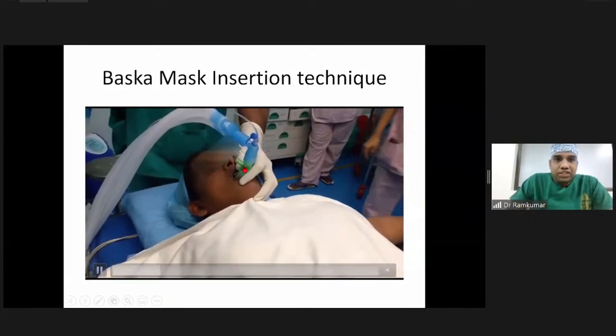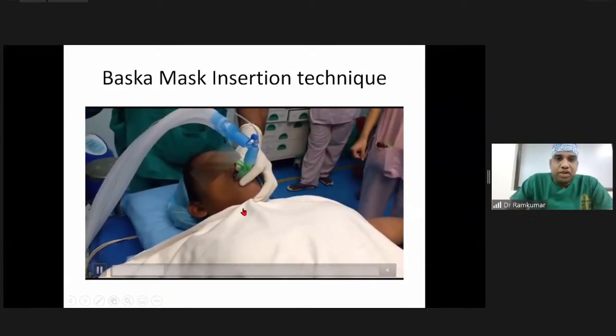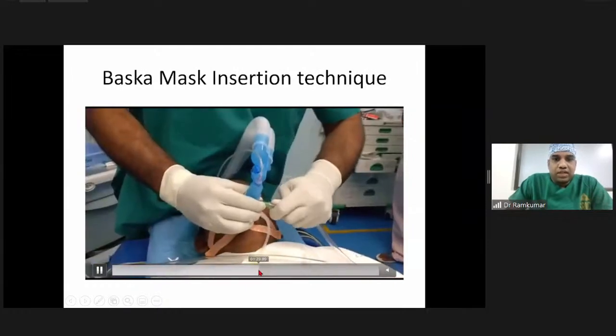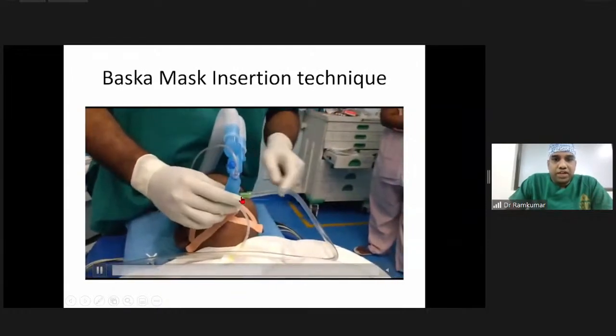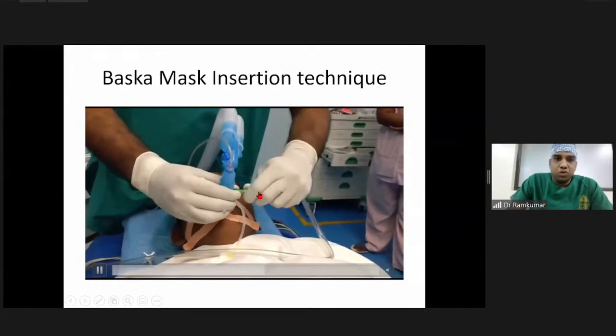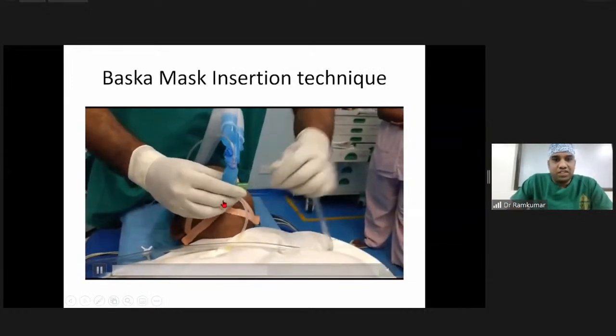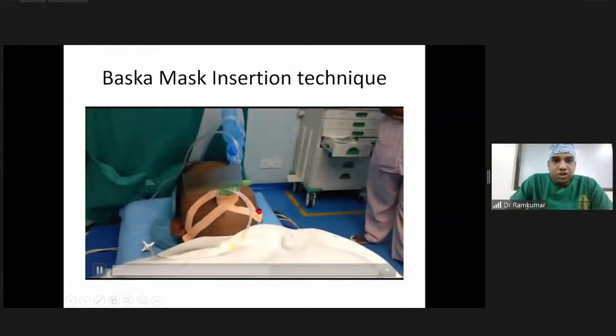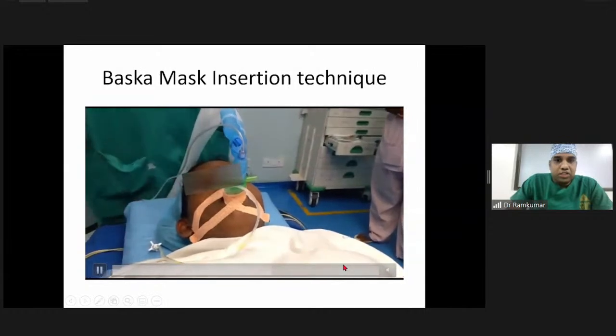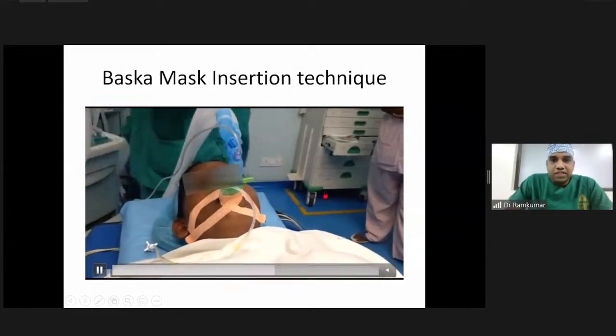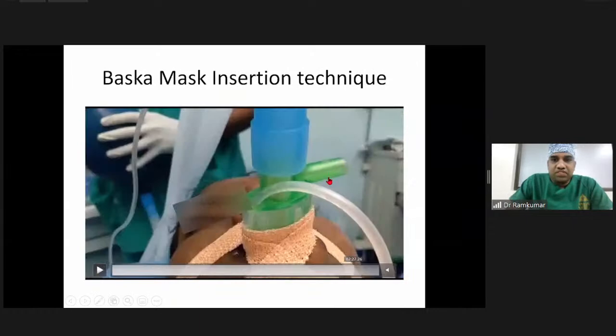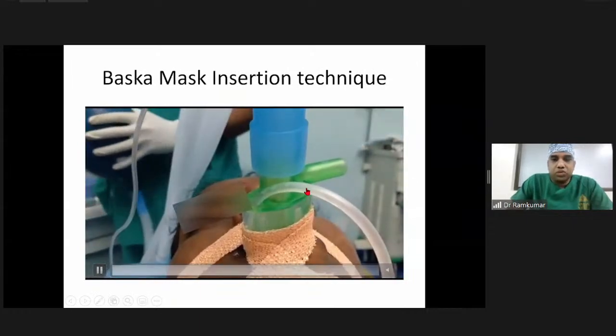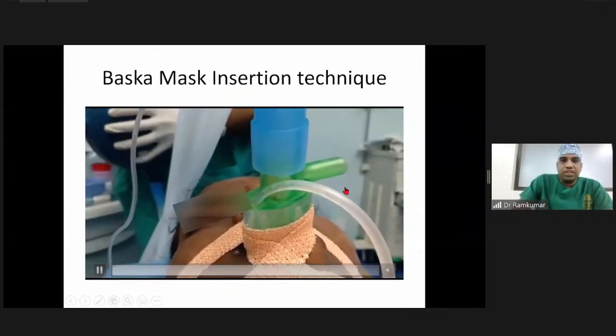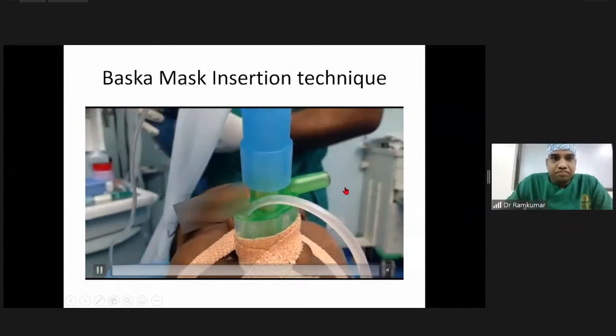And the advantage is you can use this drain, suction elbow on either side. I'm suctioning the drain tube. This is the only device where I can do a hypopharyngeal suction as well as a gastric suction, and you can pass the Ryle's tube into it. That's the advantage of the device. There's a Ryle's tube on the other side, and this is kept as a vent. You cannot do suctioning on both sides. One has to be kept as a vent to avoid mucosal injury.